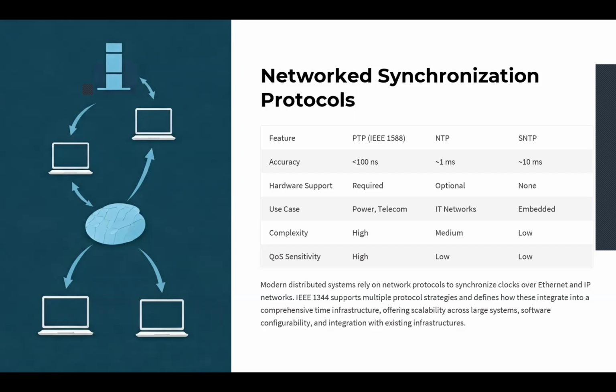Now, on the other hand, NTP, the Network Time Protocol, is designed for internet scale systems like servers, enterprise networks, or web infrastructure. It has an accuracy, as we said, of about 1 to 10 milliseconds in ideal conditions. It uses statistical filtering, delay compensation, and jitter smoothing. The communication this protocol uses is normally UDP over IP. This protocol is not ideal for high precision control, but it is excellent for distributed logs.